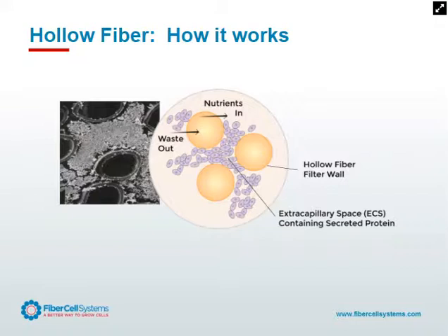This high cell density allows us to culture cells for extremely long periods of time and to grow cells in three dimensions. Passage number is irrelevant and splitting the cells is not required. Third, we can control the pore size of the fiber anywhere from 5,000 Daltons to 0.1 microns. Small things like glucose, lactate, ammonia, nutrients, and waste products can freely cross the fiber, while larger secreted products such as proteins, antibodies, viruses, and exosomes cannot cross the fiber. They are retained and concentrated to 50 to 100 times higher concentrations than what you can get from standard bioreactors.